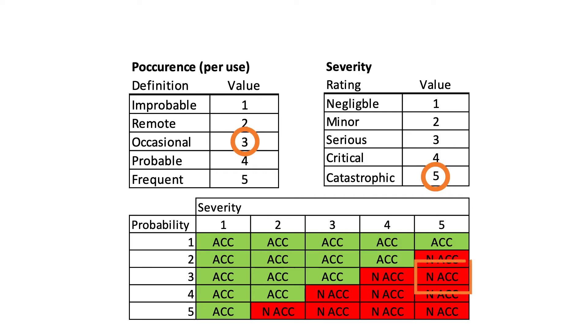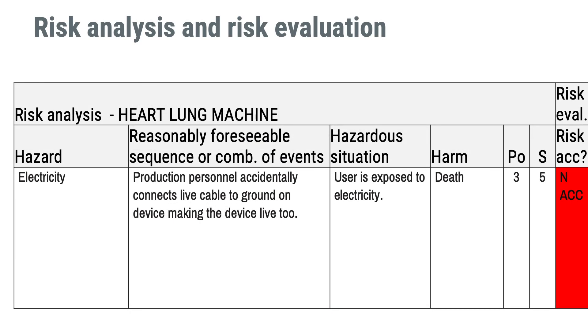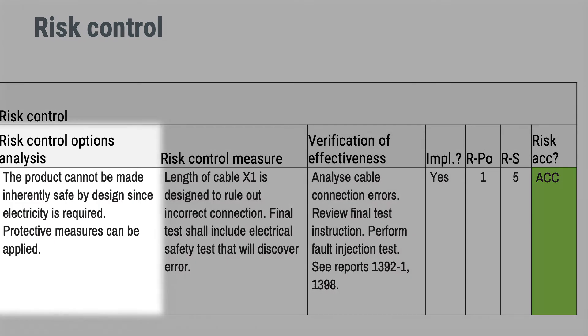This results in an unacceptable risk in the risk evaluation matrix, here indicated with NACC — short for not acceptable. The risk evaluation concludes that this risk is far from acceptable, so the next step would be to look at what we could do to reduce this risk. This is called risk control options analysis.